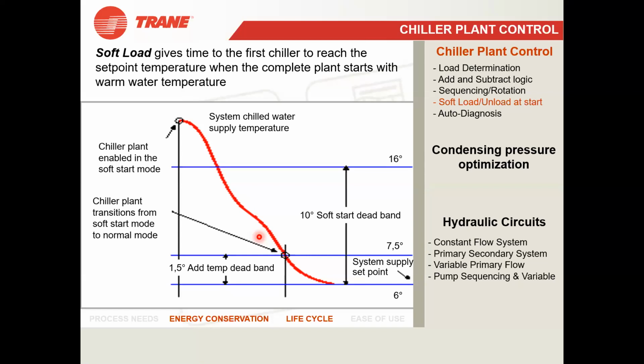So if the complete system is switched off, then what happens? The header temperature and the system chilled water temperature, both will reach the ambient. Here I can consider the ambient as 25, 24 degrees, whatever. So it will be almost equal to the ambient temperature. Then he switches on one chiller. When he first switches on the system, it will try to run only one chiller and monitor the rate of change of temperature. You are switching on the chiller, that means the air will be cooled now, right? So how fast is the system chilled water supply temperature getting cooled? If it is very fast, it will not allow another chiller to start.